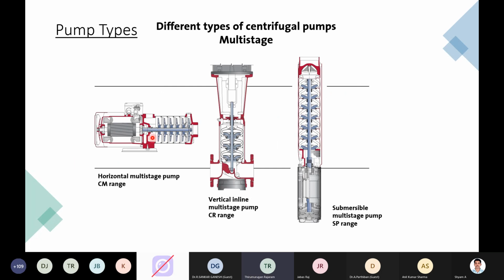Here you have a horizontal multi-stage version and a vertical multi-stage version, where you find more pressure is required to transfer the liquid. So for example, in a water treatment plant, you need a high pressure pump before your RO membrane, and your pressure is 15 bar to 30 bar. The same thing, your initial horizontal multi-stage pump, which is acting as a feed pump, or raw water feed pump, you can say, in your water treatment plant, which may be 2 or 3 bar pressure, it is able to operate.